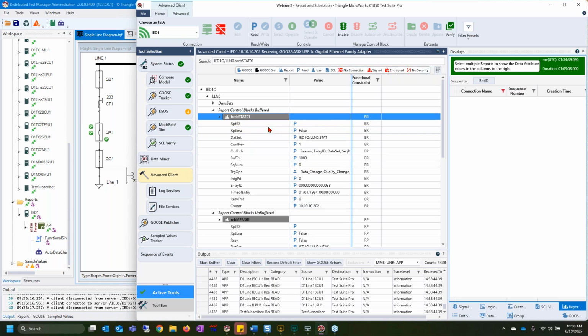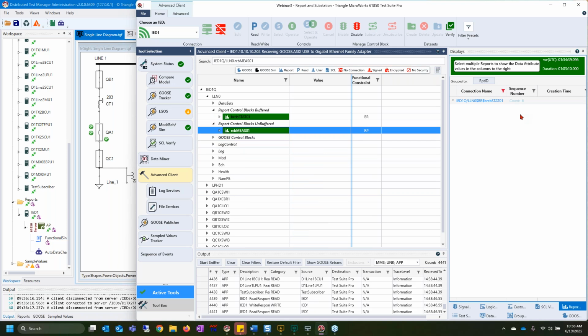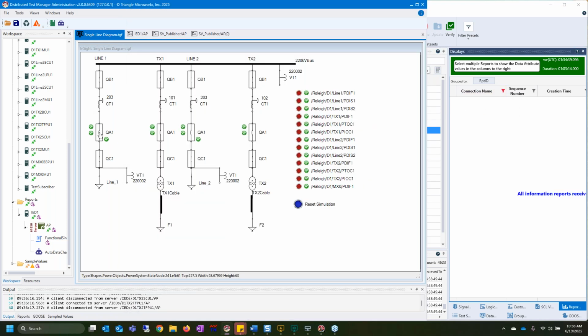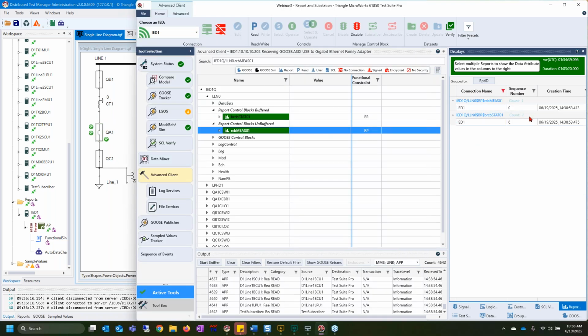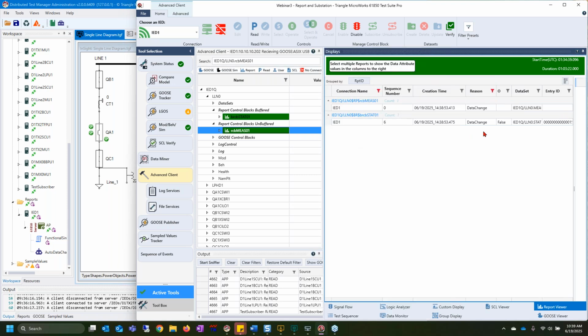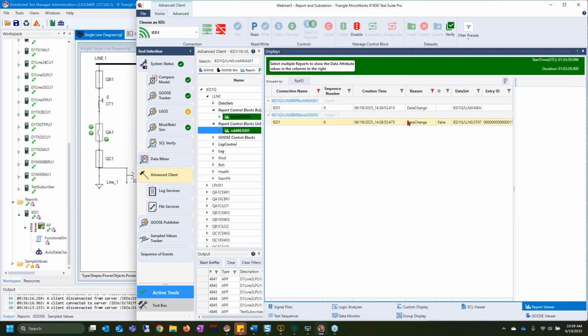So now if I come in and enable these reports here, what we will now see is, if I come over and open this breaker, the current will drop to 0, the breaker of course opens, and we can go in and see those in the reports here. As the data changes, I'm going to grab a little bit more real estate over here on the right-hand side. You can see that the measurement and the status values here have been deployed to TSP via reports, and you can see it was due to data change. If you click on the individual report, you can actually see what was included in the report.